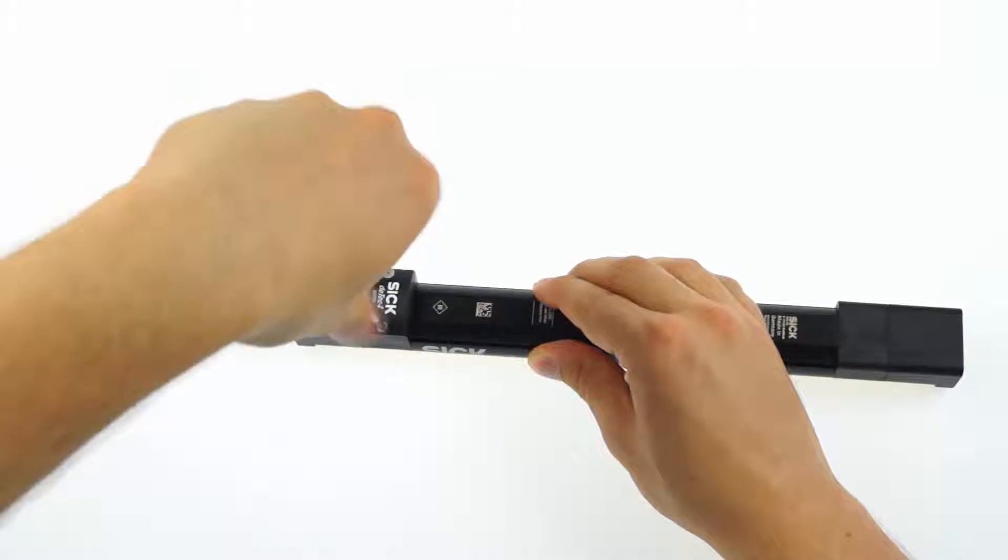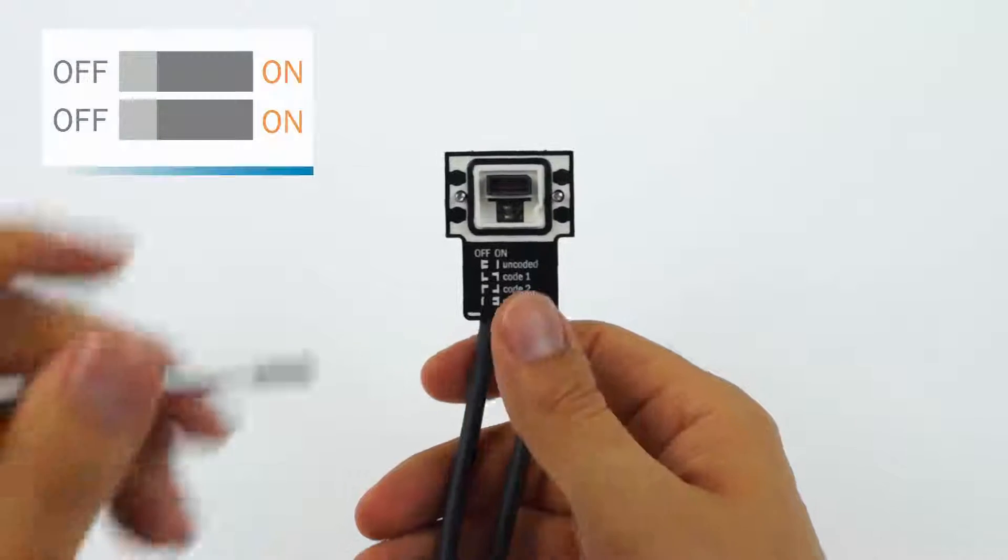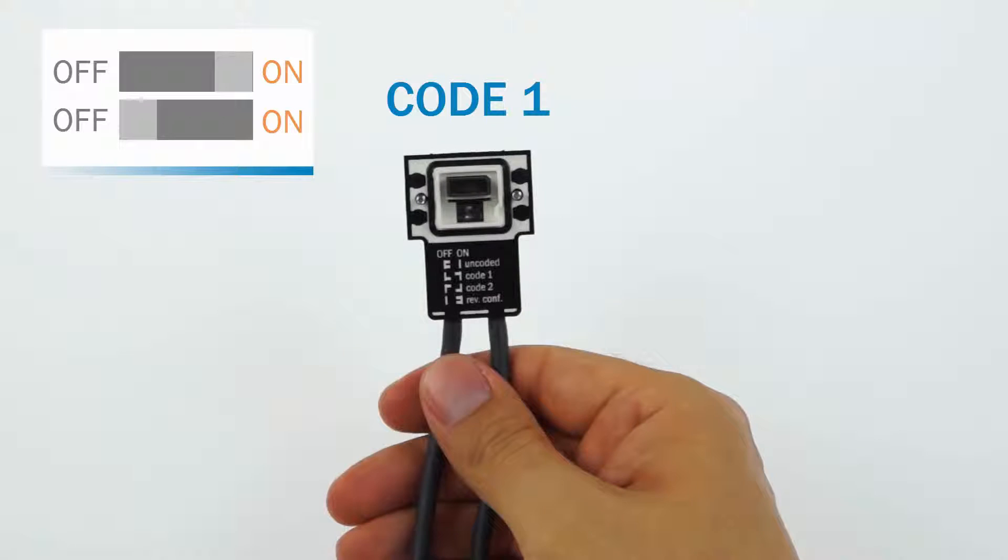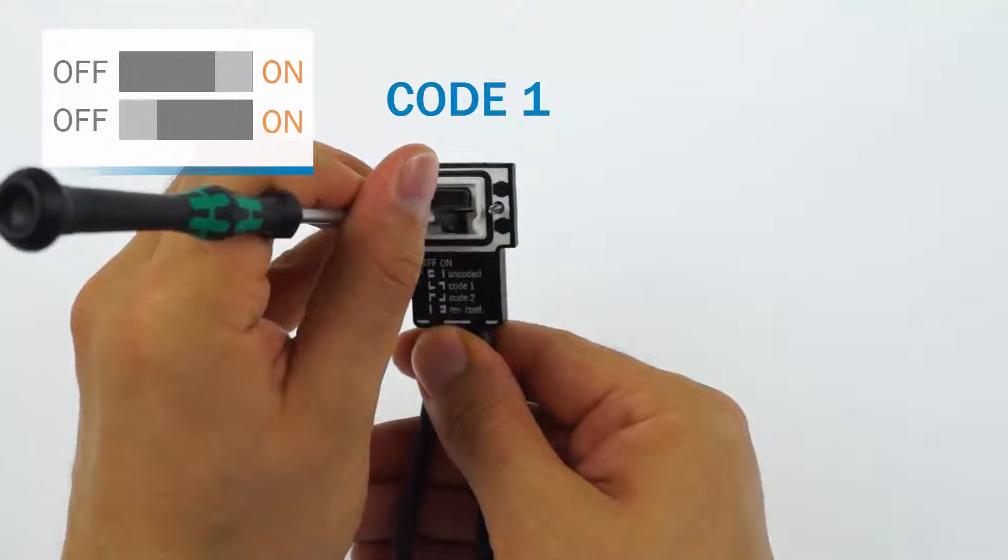Then detach the system plug by loosening the two retaining screws. On the system plug you find two DIP switches. With those switches you can set two different codes by either setting the first switch to ON and the second switch to OFF or vice versa.